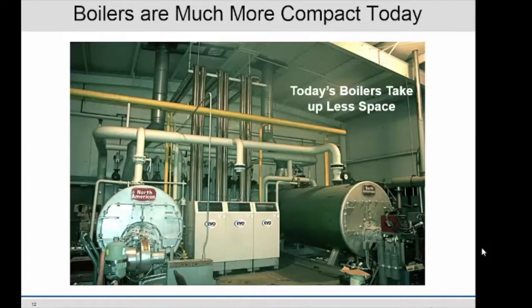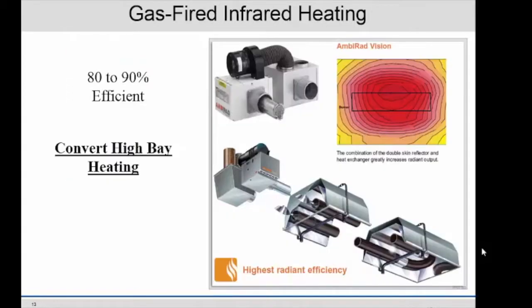Today, this is an actual installation. See how small the condensing boilers are? They're replacing these big fire tube boilers. They take up a lot less space. It's the way to go. Gas infrared: if you're getting rid of steam and you have a warehouse or a shop or some kind of high bay area like a hangar, use gas-fired infrared heating. It's much more efficient on high bay buildings. It's the way to go, I'll tell you that.